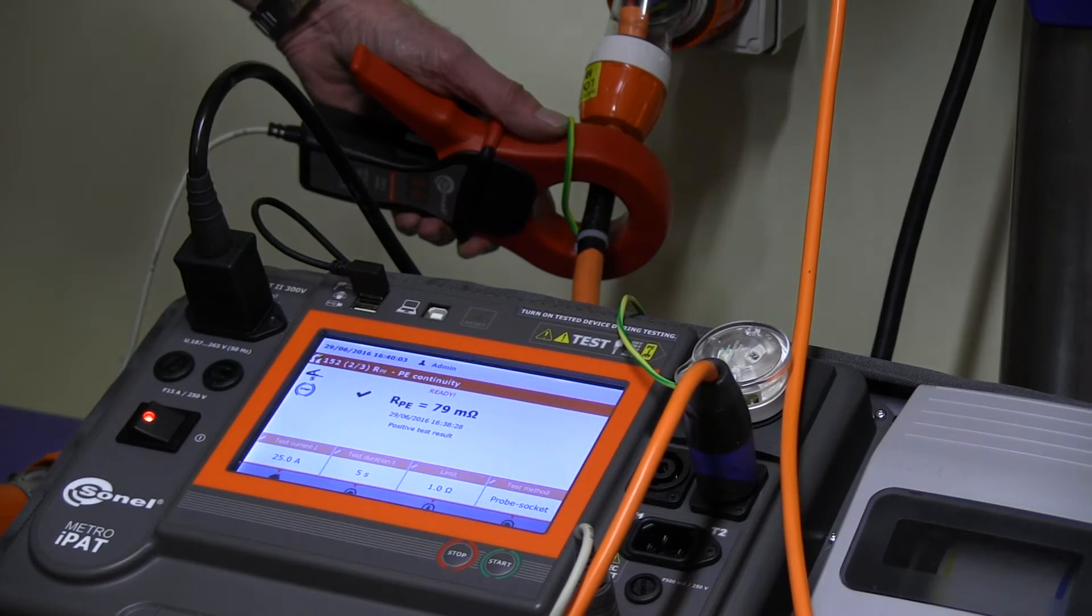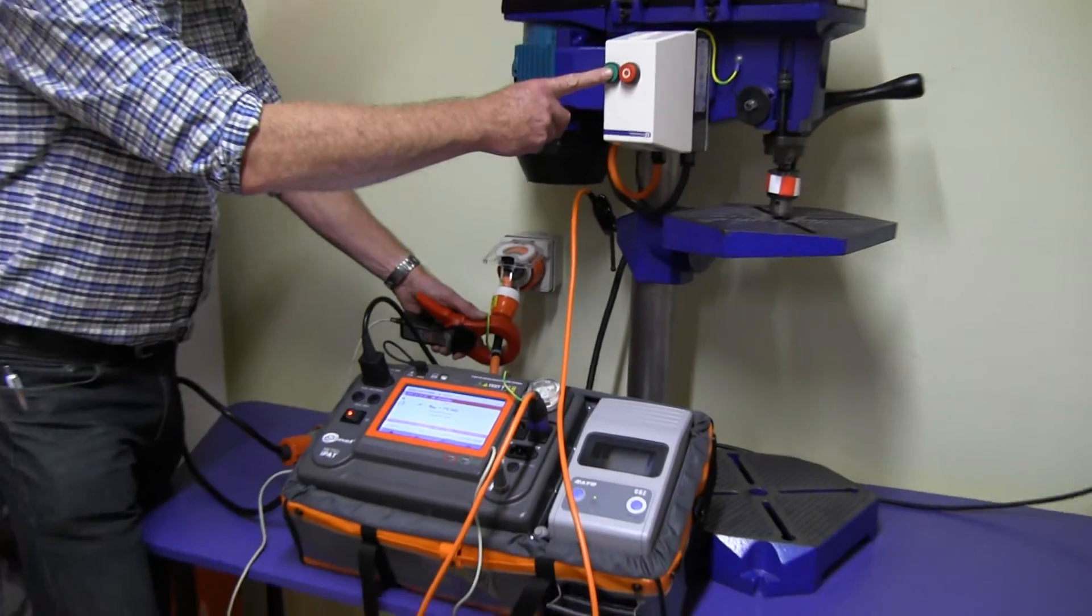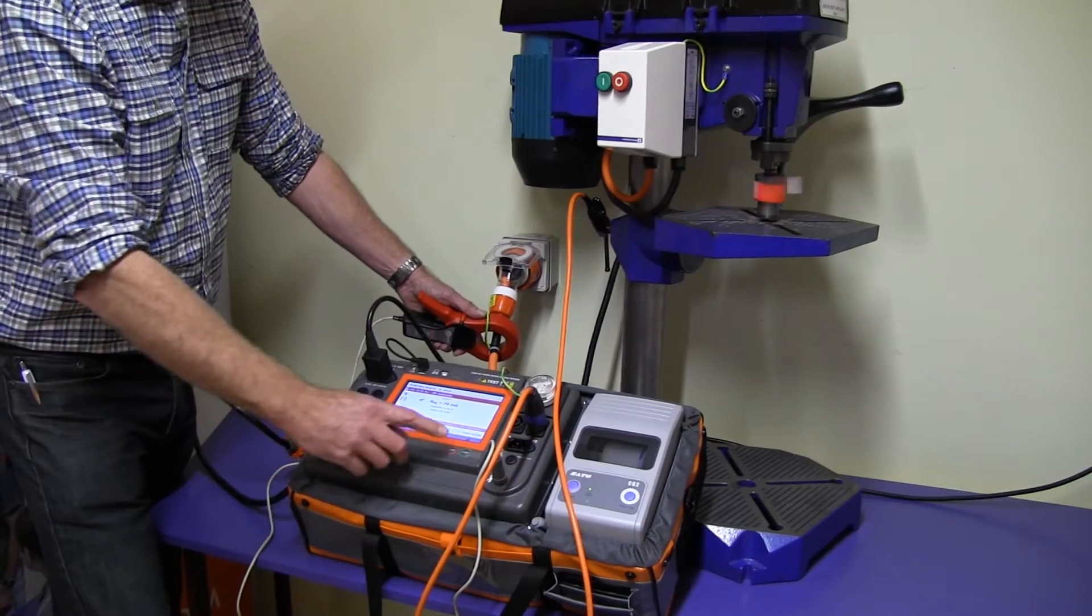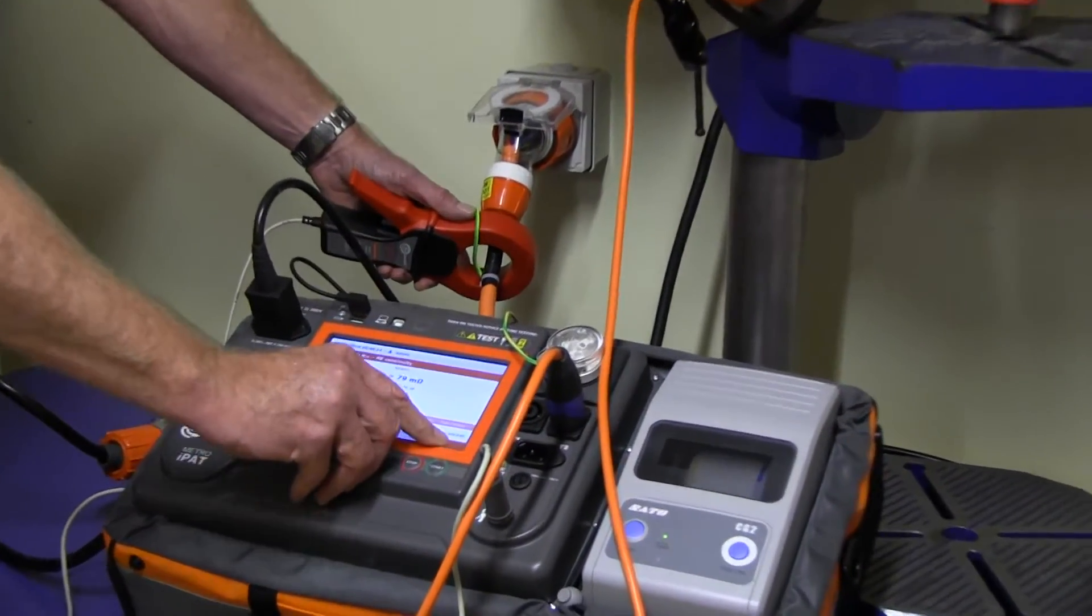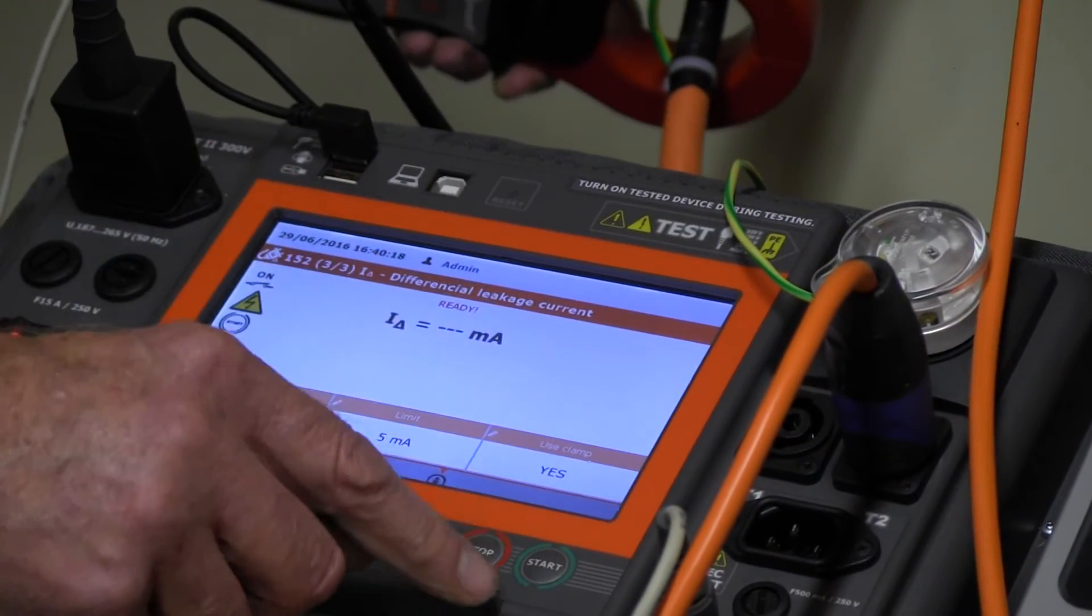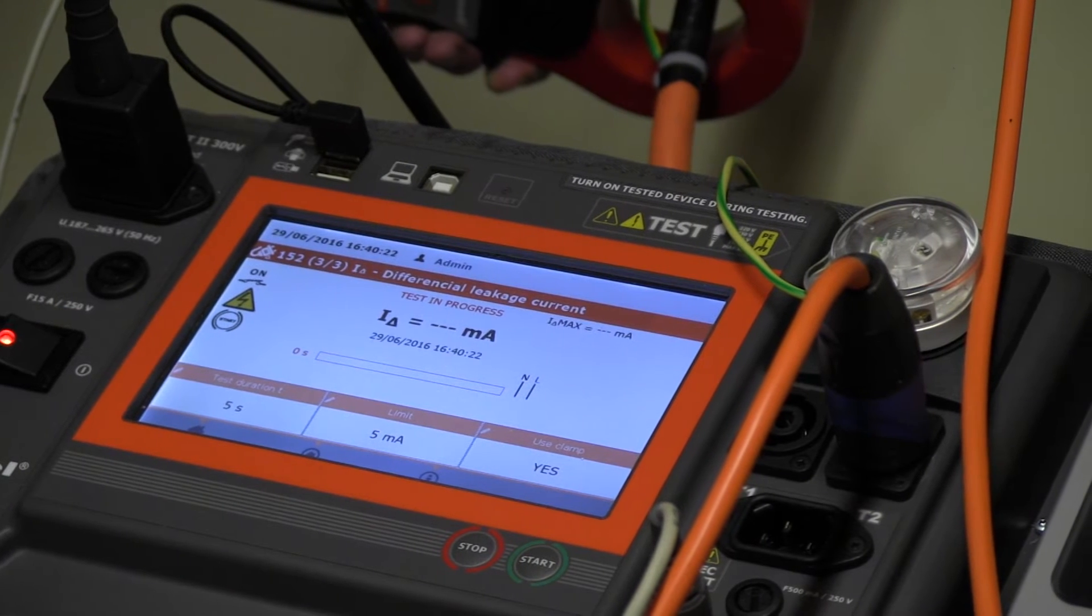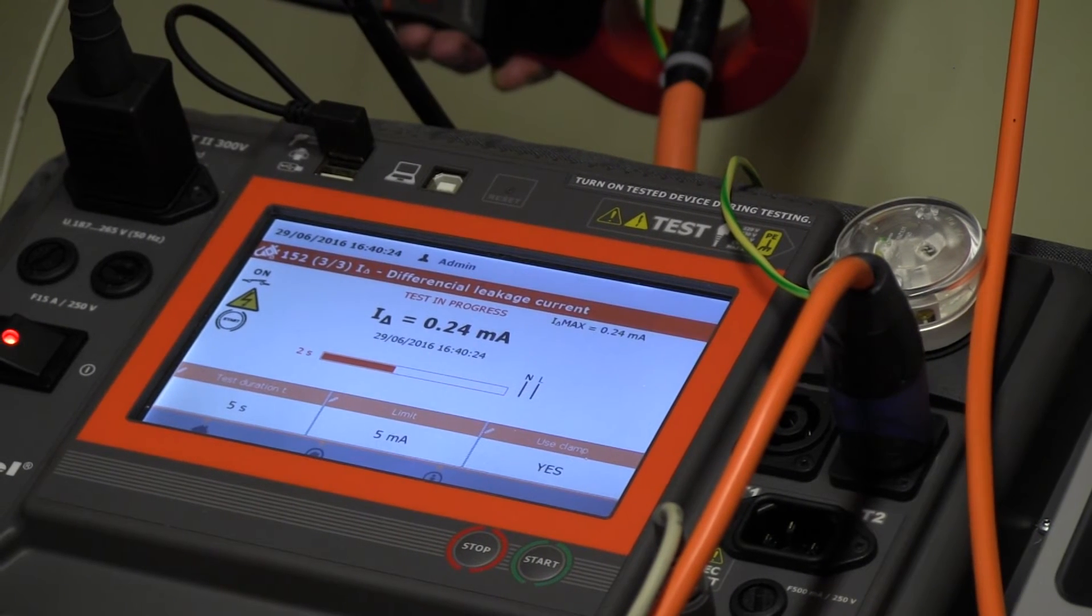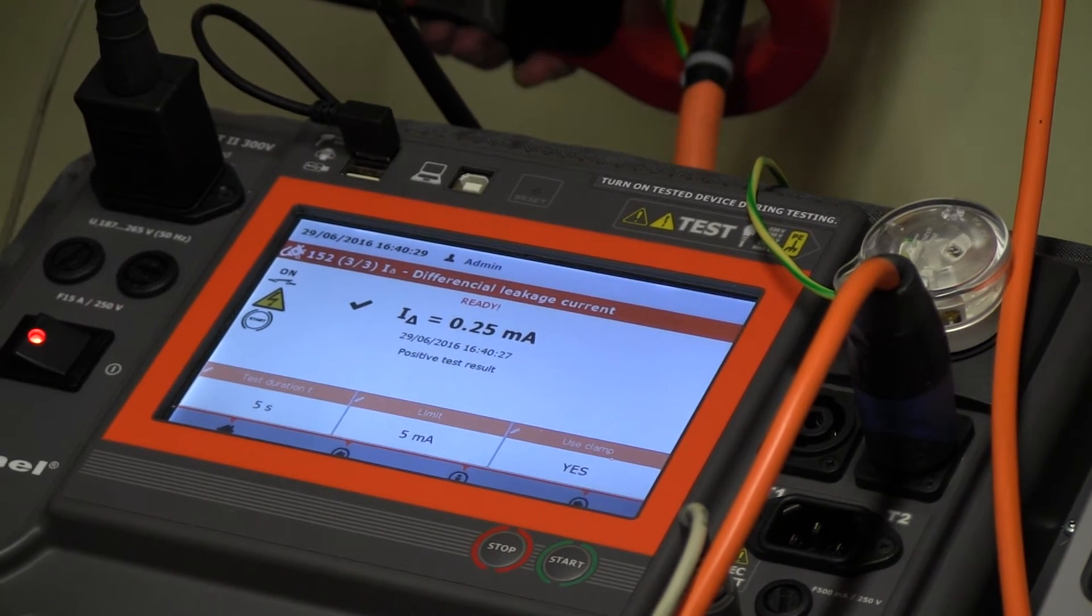At this point I start the drill press. It's running through its normal three-phase supply through the adapter lead. We press the start key with the arrow key forward. Now measuring the leakage, 0.24 of a milliamp. That's good. We can stop the machine now.